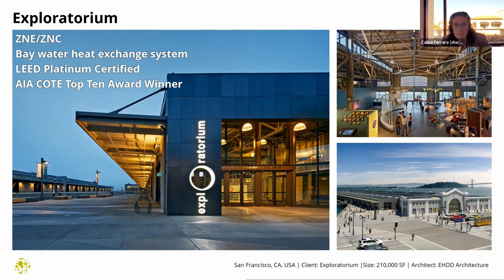When we do need to do mechanical heating and cooling, when we can't meet it with the passive systems, this building actually ties into the bay water. So you can see where that building is located right on the bay. We actually use that bay as our heating and cooling source. So we pull the seawater up through some heat exchangers.